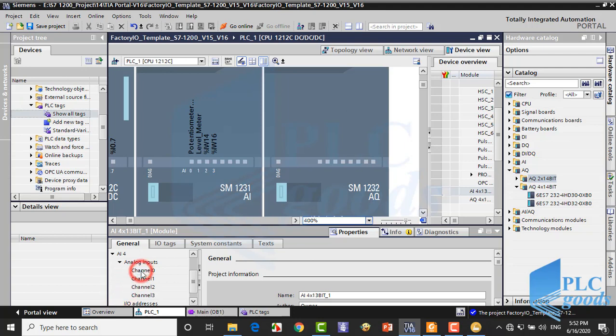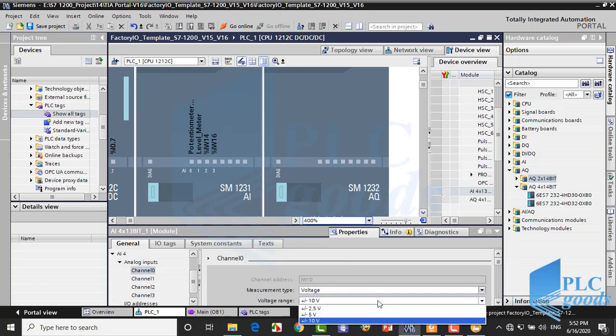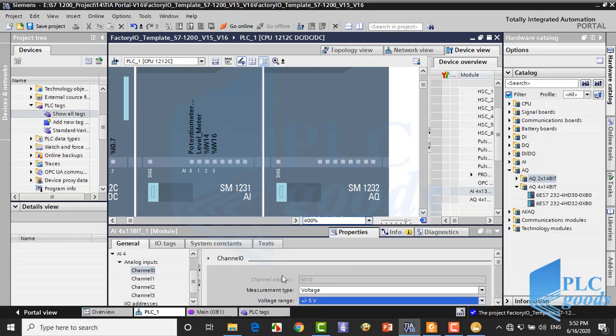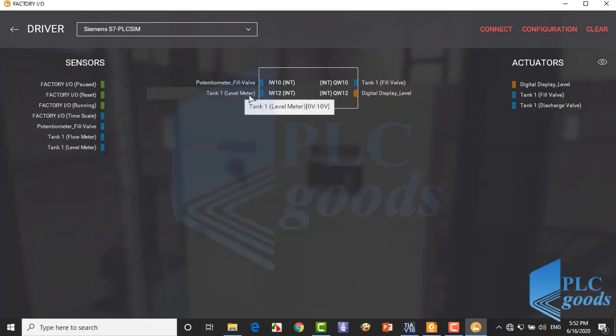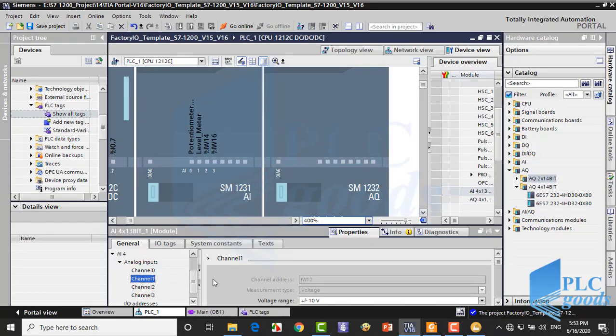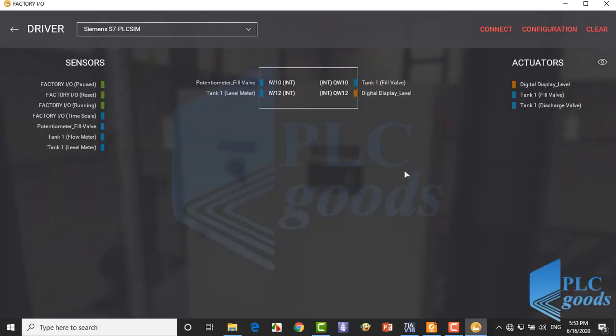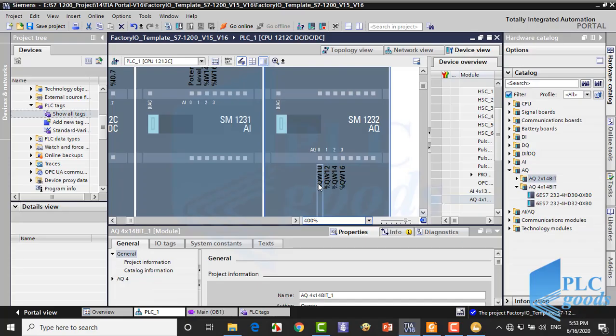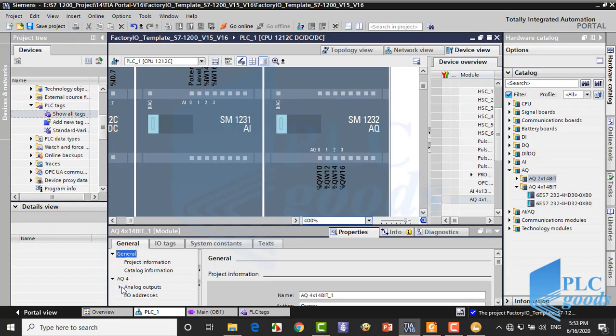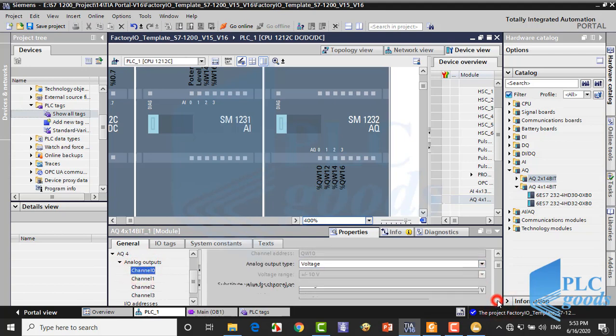The first input signal is from the potentiometer. If you remember, the potentiometer voltage is minus 5 to 5 volt, and the level meter voltage is 0 to 10. The first analog output, the fill valve, is controlled by a voltage between 0 to 10. The last output is used to send an integer number directly to digital displayer in the factory IO. That doesn't need to determine its voltage range.